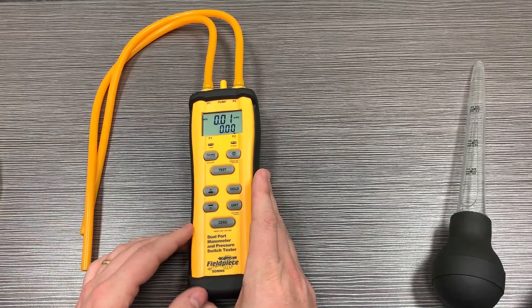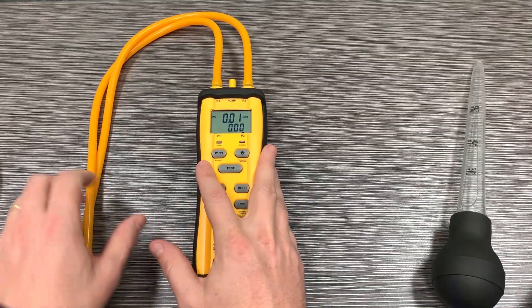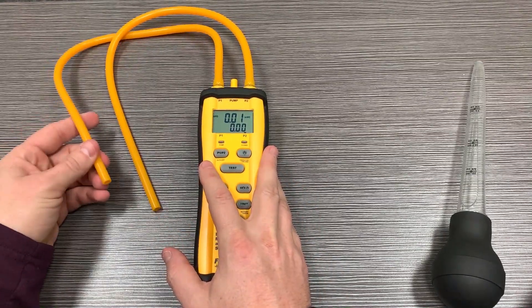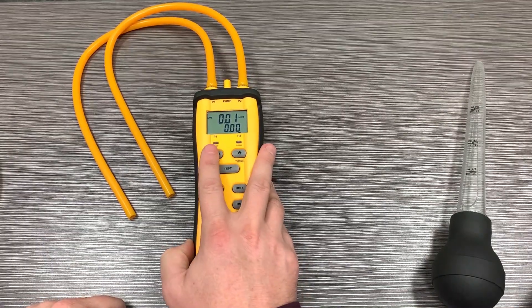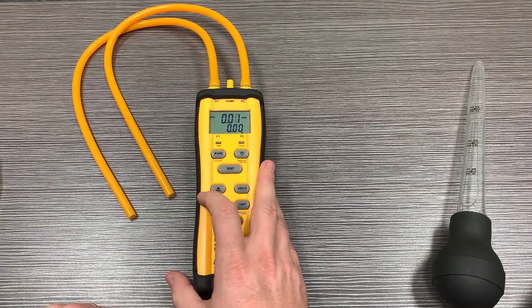If you're measuring pressure on a gas valve, you would want to be toggling. If you take one and hook it on your inlet to your gas valve and the other to your outlet or manifold pressure, you're going to want to toggle back and forth between P1 and P2 to see what those are.